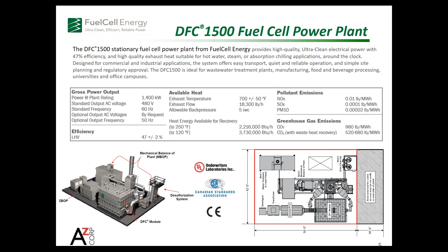You can see in the box there to the right, the pollutant emissions are really negligible, and you'll find them at least an order of magnitude lower than equivalent combustion-based systems. Output from our 1.4 megawatt system is 480 volts, and as I say, 1400 kW. The output voltage can be varied based on different transformers and so forth. Finally here, the LHV electrical efficiency is 47%, which is really, really superior in comparison to many equivalently sized combustion-based technologies. Additional efficiency advantages are definitely available by harnessing and using the exhaust heat that is exiting from the back end of the plant.